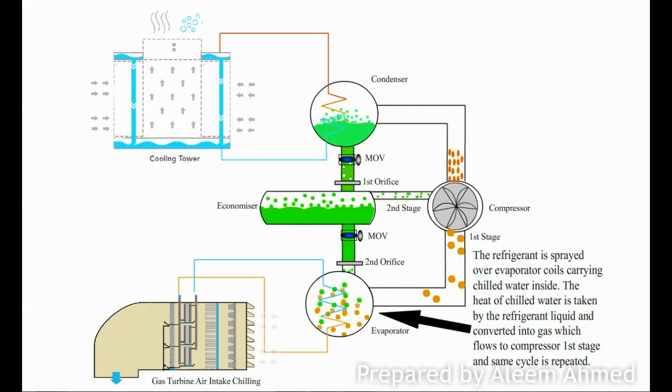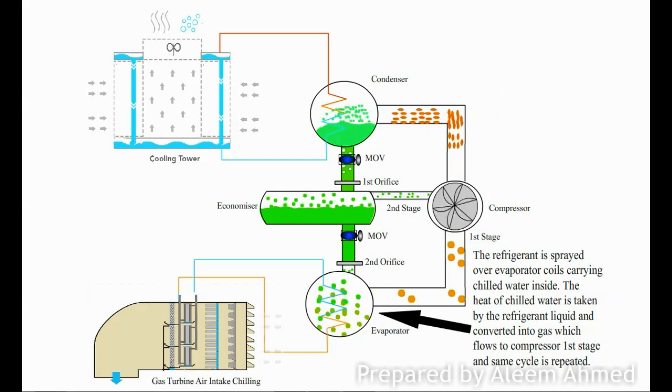The liquid refrigerant is sprayed over the evaporator coils carrying chilled water inside. The heat of the chilled water is taken by the refrigerant liquid and converted to gas.